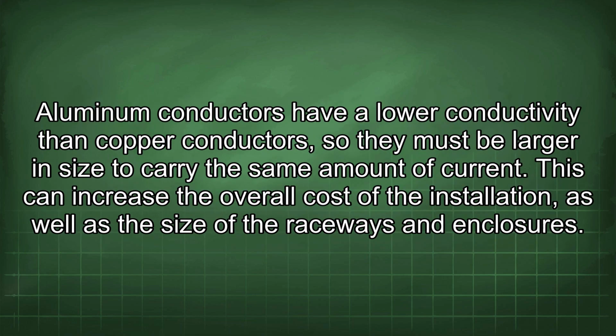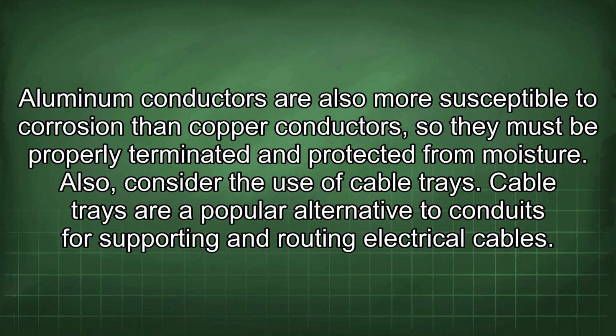Aluminum conductors have a lower conductivity than copper conductors, so they must be larger in size to carry the same amount of current. This can increase the overall cost of the installation as well as the size of the raceways and enclosures. Aluminum conductors are also more susceptible to corrosion than copper conductors, so they must be properly terminated and protected from moisture. Also, consider the use of cable trays.